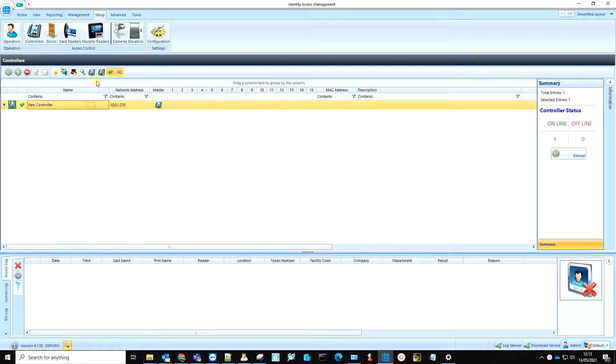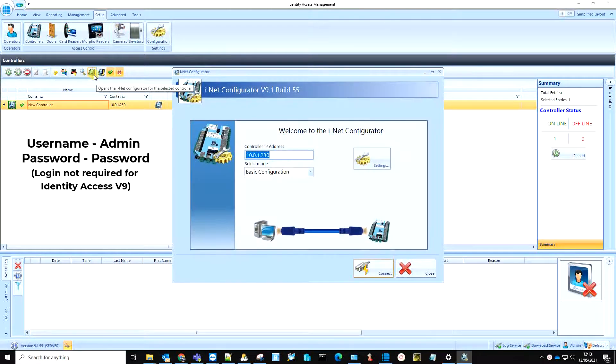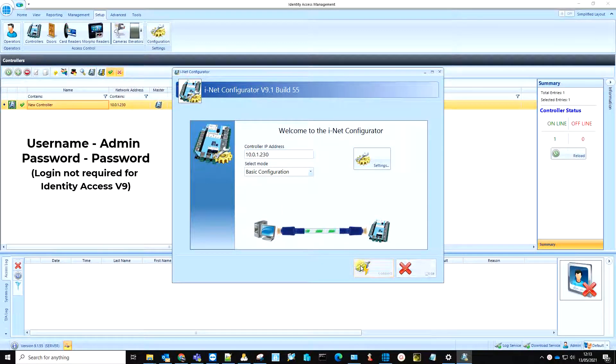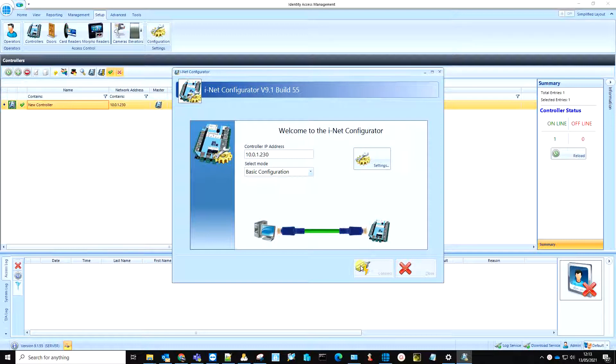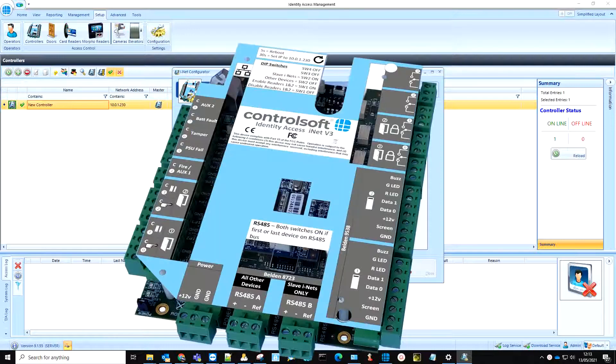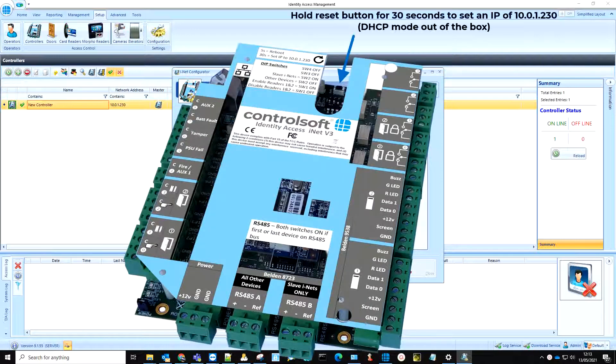We will now launch the iNet Configurator and login using the credentials shown. In this example, we are connecting to the iNet using its default IP address, which is 10.0.1.230. This IP address will be set if the reset button on the iNet controller is held for 30 seconds.